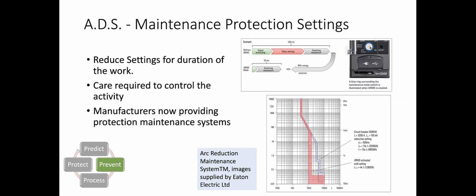But the point is, manufacturers are now providing protection maintenance systems, such as Eaton here. They recently patented a system that they call arc flash reduction maintenance system, ARMS technology, for low voltage molded case and air circuit breakers. It allows for a maintenance mode to be set on a circuit breaker, which in effect provides a lower instantaneous pickup level via a separate maintenance setting. And when fitted, it operates independently of the main protection.